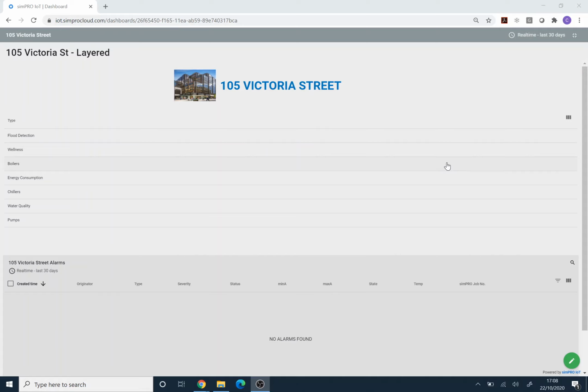Each sensor can be set up to individually monitor for readings above and below a threshold specific to that particular piece of equipment it's connected to, and trigger alarms both on the dashboard and via email alerts in the event of equipment going out of threshold. From this dashboard, you can access all of the various areas being monitored. In addition, all the alerts can be seen on the widget at the bottom of the screen, although there are currently no active alerts on this particular site.